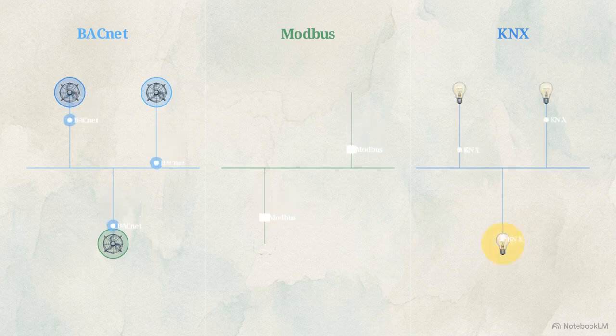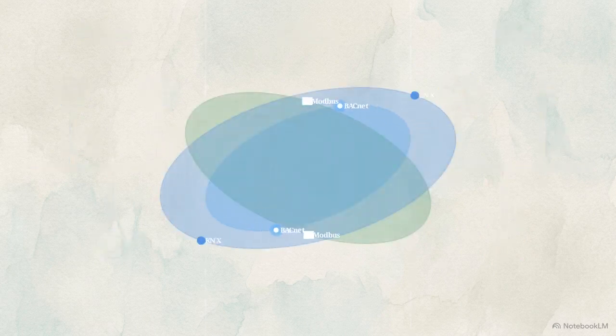The dominant protocol for modern commercial HVAC systems is BACnet. As an open standard, BACnet allows equipment from entirely different manufacturers to communicate without requiring custom integration. Alongside BACnet, you will frequently see Modbus. It is an older, simpler protocol, but it remains highly reliable and is widely used for connecting heavy industrial equipment and energy meters. In European deployments, KNX is the common standard, particularly for managing lighting and shading systems.